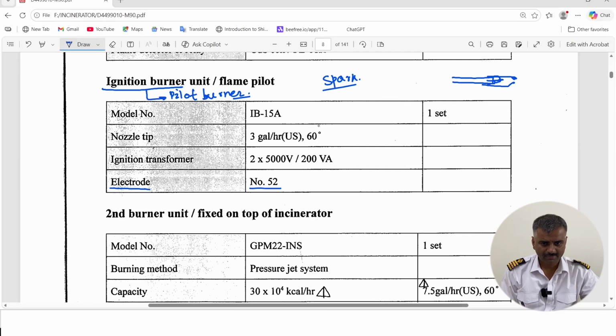Now the question. This distance. So first let's discuss the electrodes over here. Electrodes number 52. This distance between the electrodes is said to be around 2 to 3 mm gap. When this distance is disturbed, if you increase or reduce this distance, there is a chance that the flame will not take place. Spark will not take place and the flame will not take. Spark even may take place, but the flame will not be there.